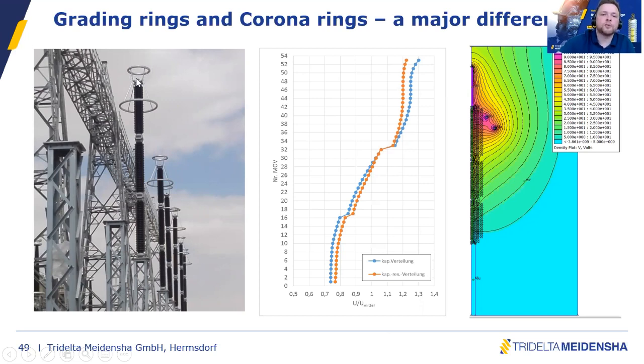The corona ring is always on top of the surge arrestor. You will never see it hanging down. And the corona ring will improve our so-called RIV performance. RIV is something that comes from the EMC standard, so electromagnetic compatibility.